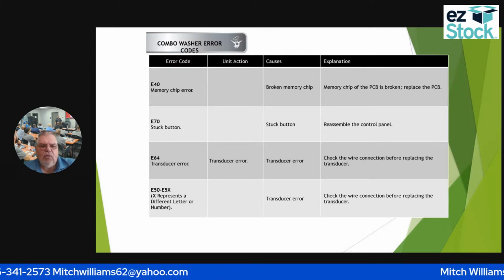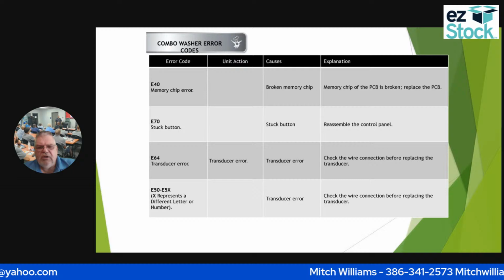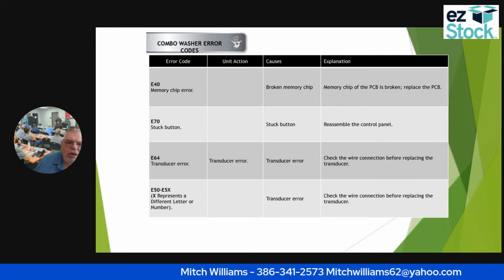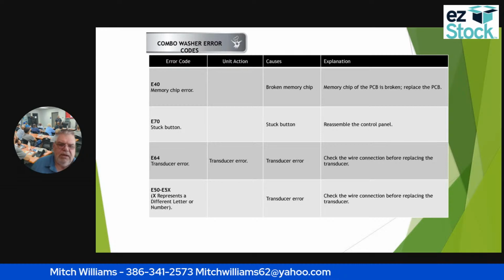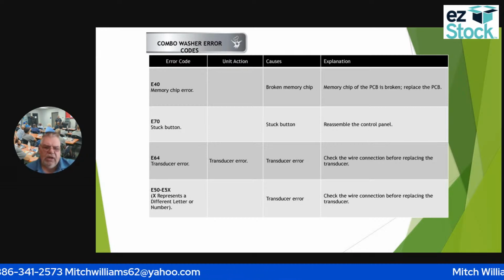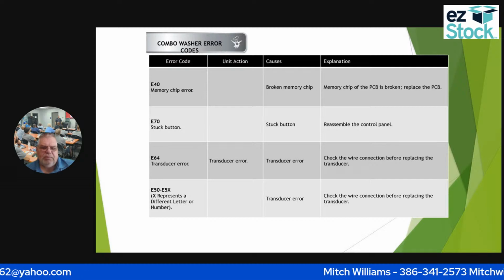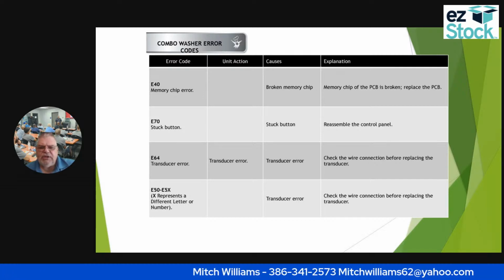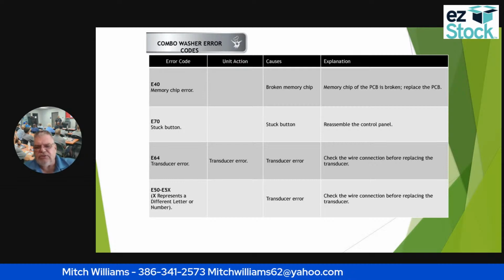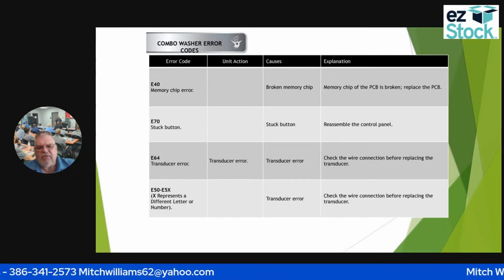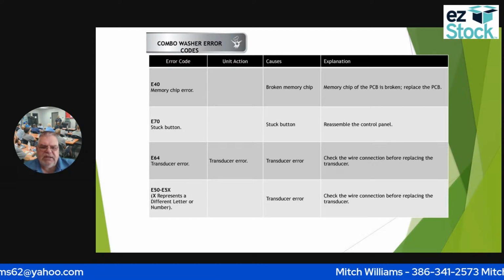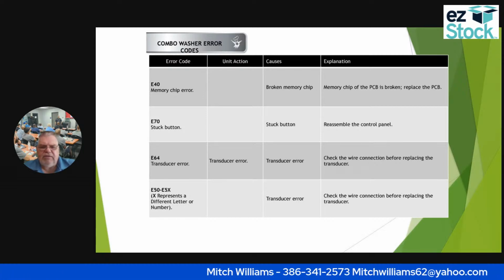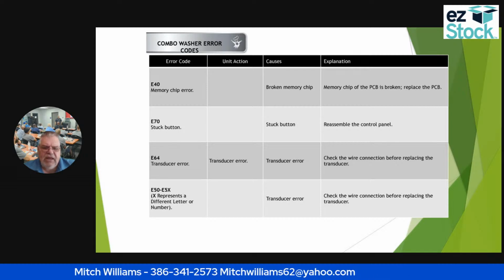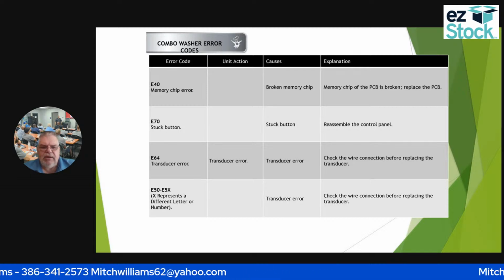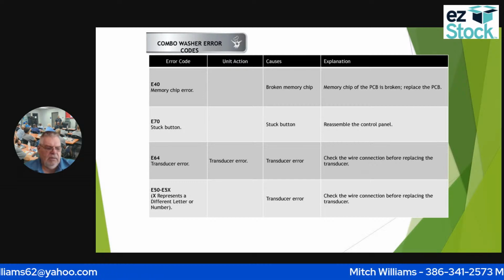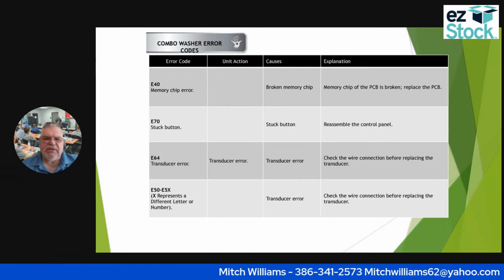Okay. E64, I have a transducer error. So the only thing I can do is check that wire. And then if that doesn't work, I'll have to replace that transducer. Okay. If I have an E50 or an E50X, the X represents a different letter or number, I have a transducer error again. I'll have to check the connectors. And then if that doesn't work, I'll have to replace that transducer. So if I have an E64, an E50, or an E53, an E5X, that tells me that I have a transducer error, and I'm going to have to go check the wiring to it, or I'm going to have to replace that transducer.